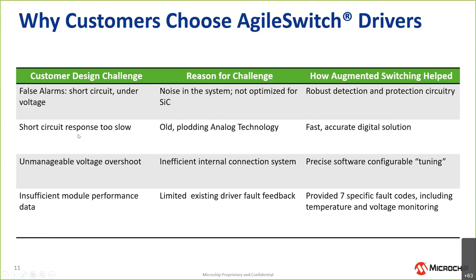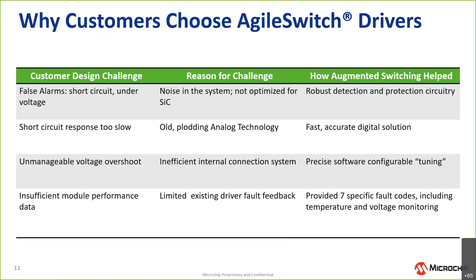A short circuit response which was too slow, based on more of an analog approach to short circuit detection - our fast, accurate digital solution helped solve that. Voltage overshoot, again another major issue in driving silicon carbide devices. Often that's due to an inefficient internal connection system. Precise software control allows for tuning, where through changing values on a screen, you're able to find that tradeoff between voltage overshoot and efficiency. And overall, insufficient data about the module itself and how it's performing. Most drivers have very limited fault feedback. We provide up to seven specific fault codes, including real-time temperature and voltage monitoring.